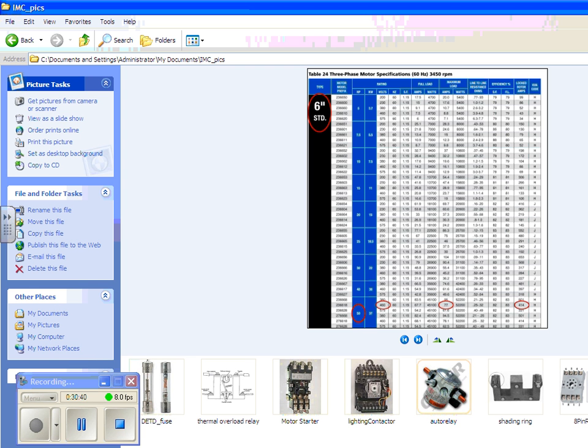Okay, so this is going to be the top page of your motor overload heater element selector guide, which I'm going to give you soon. And then we're going to start working out of that. So look that chart over on page 69 fairly thoroughly. If you believe you'll be working in Europe or someplace where they use IEC more often, you might want to look at page 71, the IEC motor starter selection guide. Notice there's a lot more of them. You might say that they're more narrowly sized.